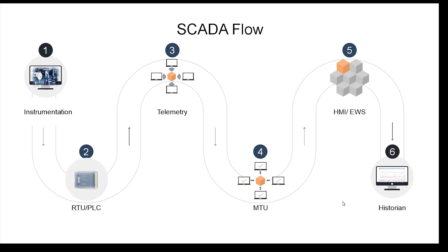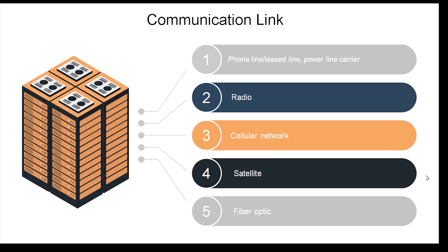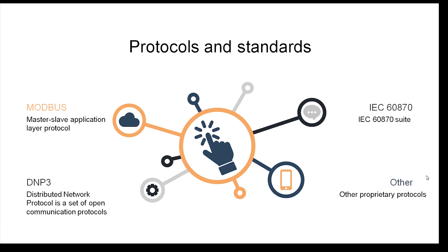To summarize: first you have instrumentation, then you can have an RTU, PLC, or DCS. In between there is telemetry — the communication layer using radio, cellular, satellite, or fiber — going from the RTU, PLC, or DCS to the MTU. The MTU connects to the HMI for visualization, the engineering workstation for programming, and the historian for storing historical data. Regarding protocols, the important ones to understand are Modbus, IEC 60870, and DNP3.